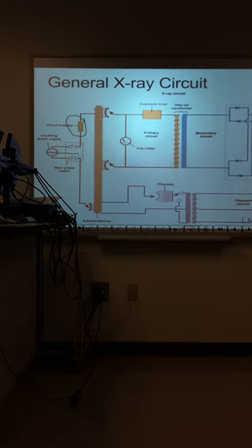You're coming in here, and because your auto transformer is so long, it fluctuates through all these ripples. This is at the control panel, so this is communicating with the control panel. Whatever I set there is communicating from here to here and comes back to make sure the output is proper. But the timer is saying, okay, someone set a kVp of 70. How much time do I need to have this on before I shut it off? It gives the system an adequate amount of time to make sure the exposure is 70 kVp. It goes back and forth multiple times for as long as it's needed.